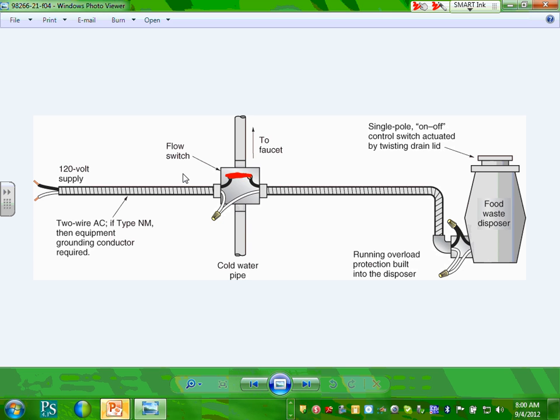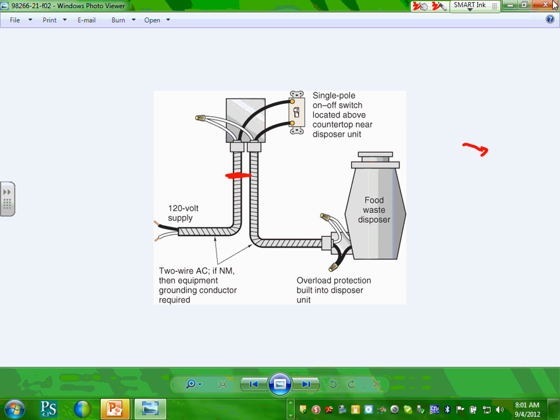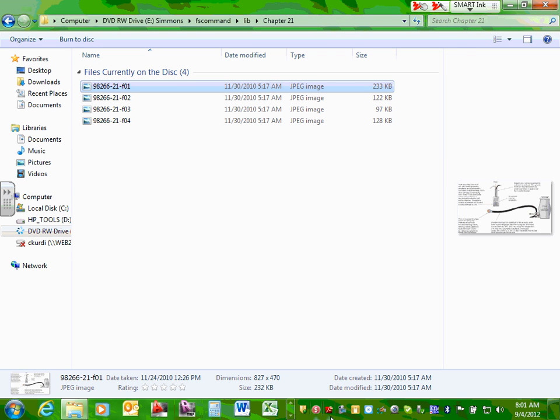Basically, the equipment is not running yet. It's just closing a contact. You still have to come over here and twist the lid in order for this appliance to work. What this prevents is energizing or activating the appliance without water going through it. Can I have a thumbs up, Chad? This preps you for how to do control. So that's safety: you can't run it unless the water's running. Cool. Has anybody installed any of these, Darren, Jeff? With a tiny little flow switch that controls it. Okay, so that's basically what we're up to. That's all we have, guys, in terms of the garbage disposal.